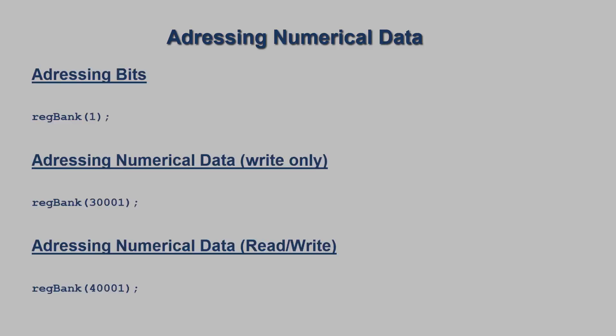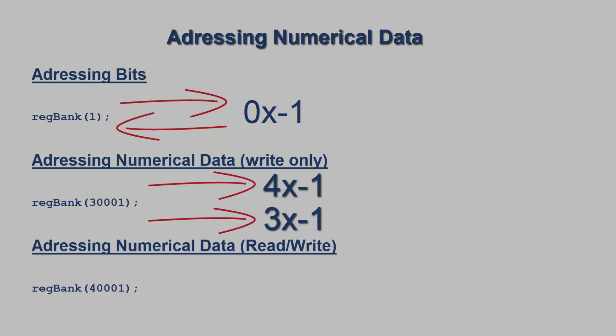Addressing numerical data is very similar to our previous video where we addressed bit addresses on our HMI. However, there are a few key differences to keep in mind. For example, how we addressed the first bit: RegBank 1 would address the 0x1 on the HMI. RegBank 30001 is a write-only register for numerical data and will be writing to the 3x and 4x registers on the HMI.